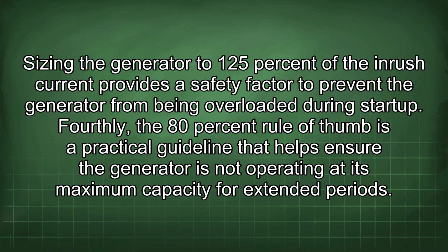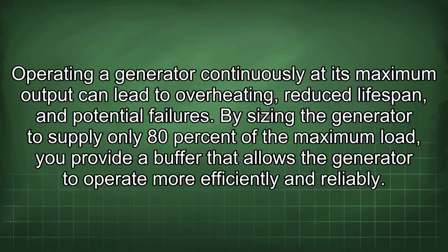Fourthly, the 80% rule of thumb is a practical guideline that helps ensure the generator is not operating at its maximum capacity for extended periods. Operating a generator continuously at its maximum output can lead to overheating, reduced lifespan, and potential failures. By sizing the generator to supply only 80% of the maximum load, you provide a buffer that allows the generator to operate more efficiently and reliably.